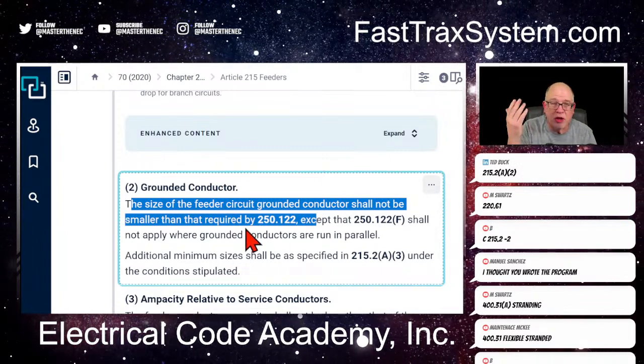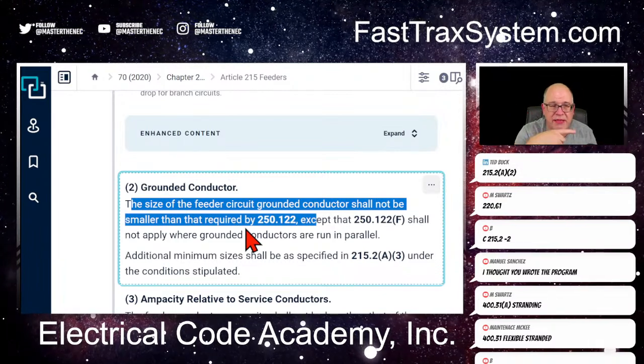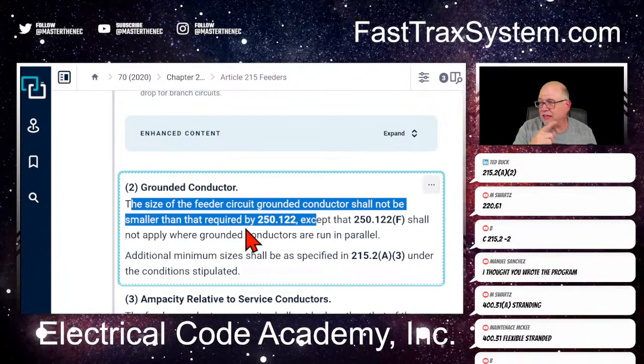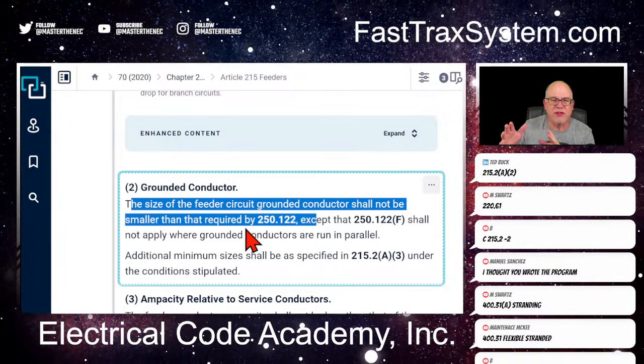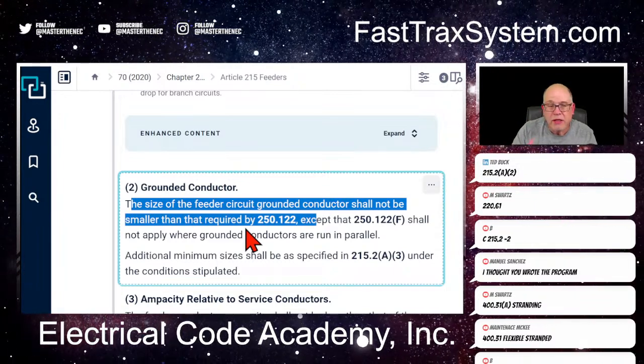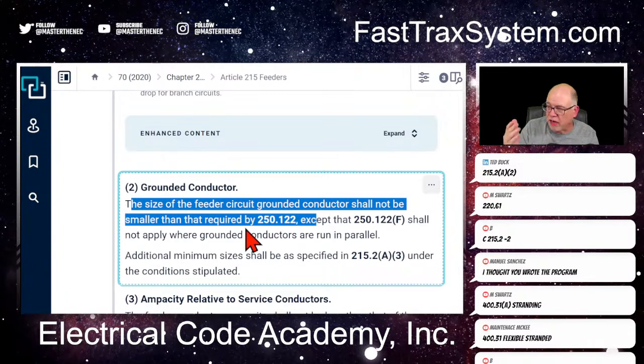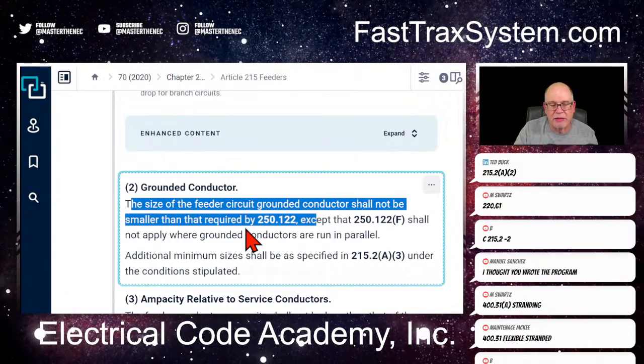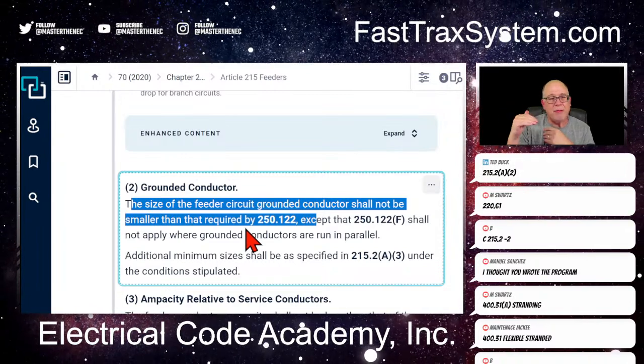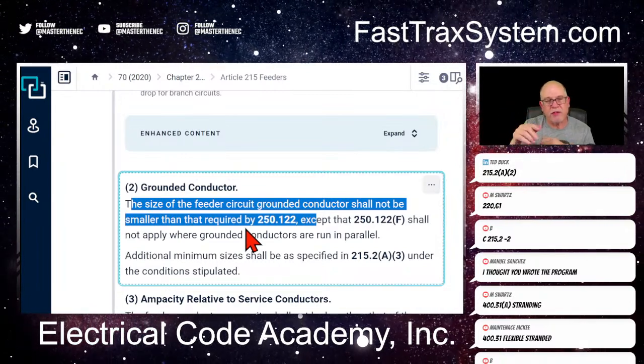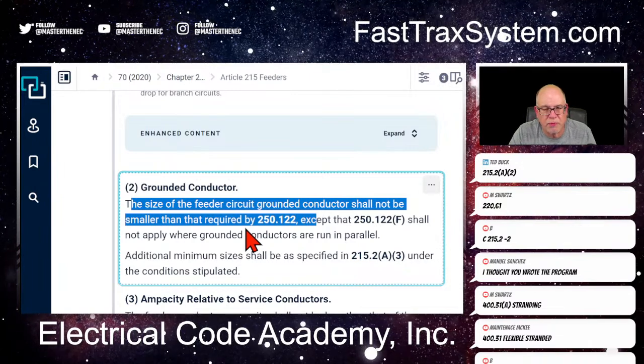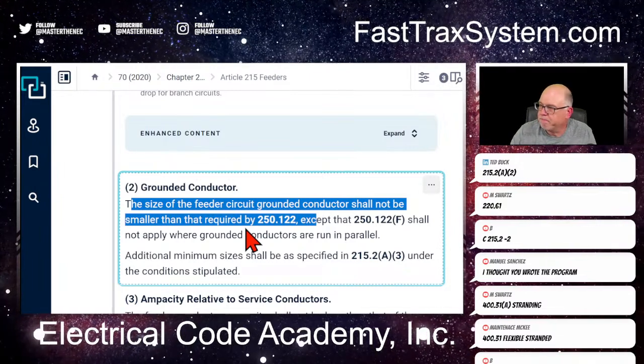And of course, since it's talking about 250.122, that means it's about the overcurrent device sizing, because that's all 250.122 driven; the overcurrent device drives the size of it. So basically, what it's saying is that your grounded conductor cannot be smaller than your equipment grounding conductor. They're going to be sized the same. So that's a minimum. But you all know that you're going to have to do a load calc, and your neutral's probably going to be larger. Okay.